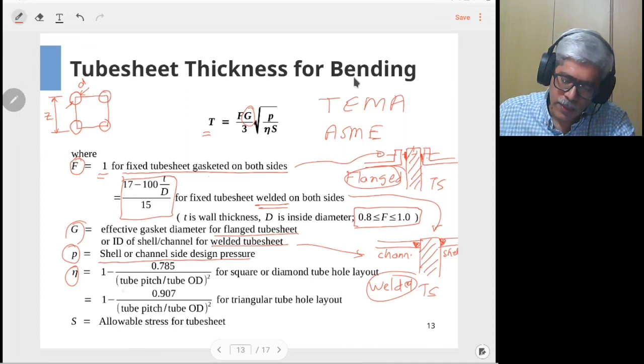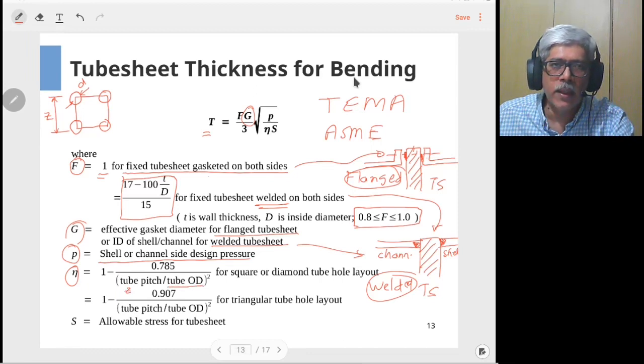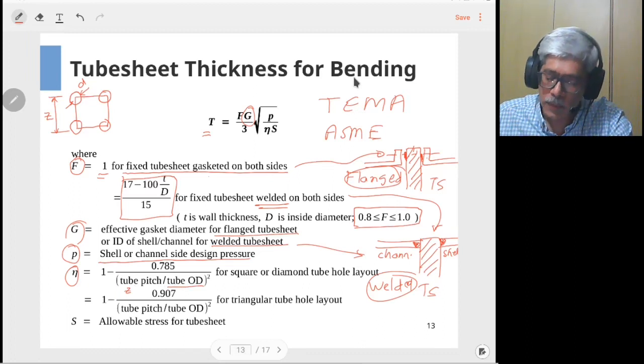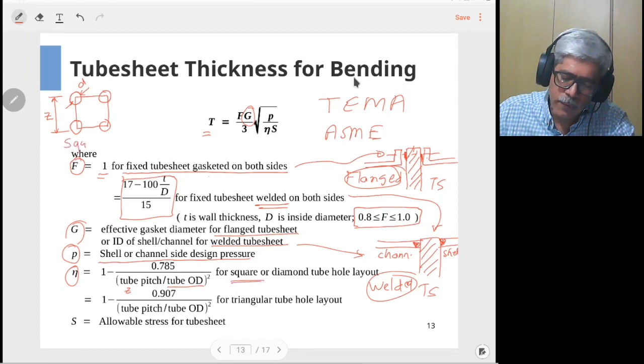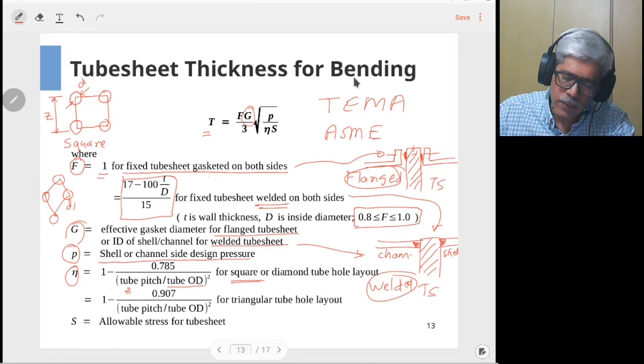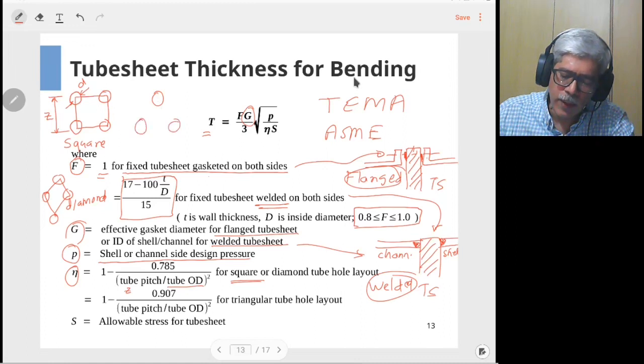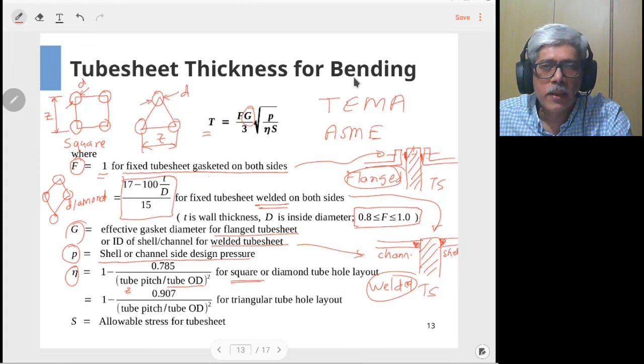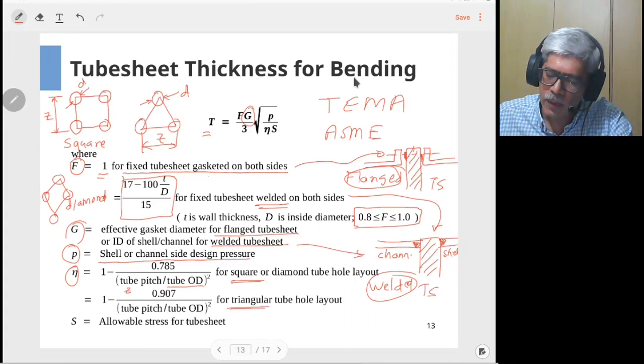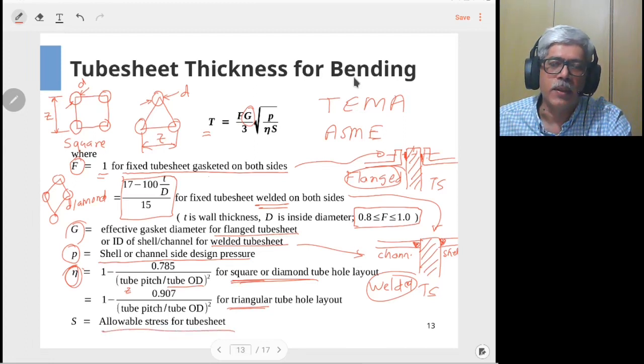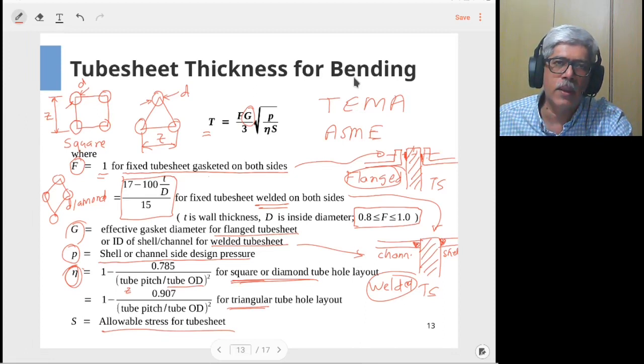The tube pitch is Z and the tube hole diameter equals the outside diameter of the tube. This ratio defines the ligament efficiency for the square layout. For a diamond layout, the tube holes are oriented diagonally. For a triangular layout, tubes are arranged in an equilateral triangle pattern, and the pitch and hole diameter define efficiency similarly. Depending on whether you have a triangular, square, or diamond layout, the efficiency factor η is calculated separately. Finally, S is the allowable stress for the tube sheet material.